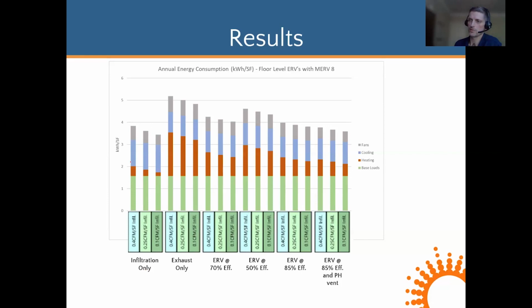We have our infiltration only scenario on the left, and then exhaust, and then our 4 ERV scenarios with varying effectiveness, and the one on the right is that Passive House ventilation level. So we can see in each scenario, by reducing infiltration, we save energy. Better air sealing means reduced heating energy and conditioning fans. The infiltration only scenario here is just for reference. Obviously, this is not allowed by code anymore, but it is important to think about because this is still the case in a lot of existing older residential buildings that rely on windows and doors for ventilation.